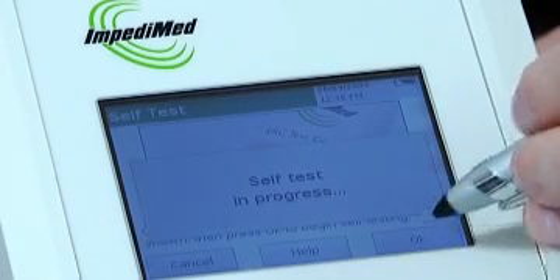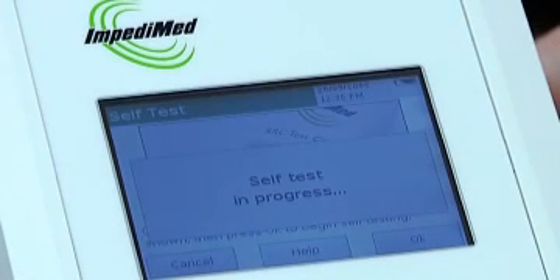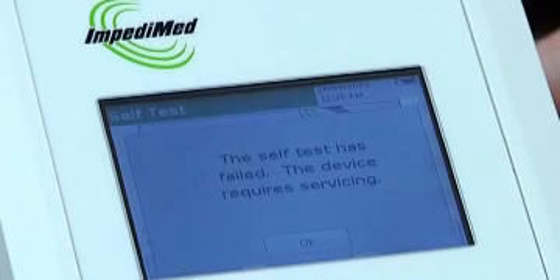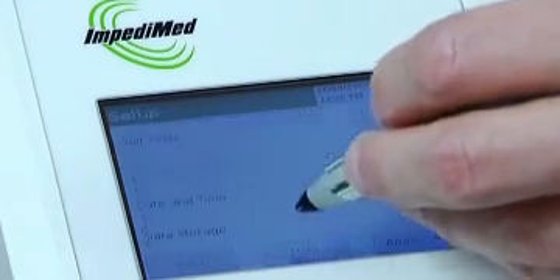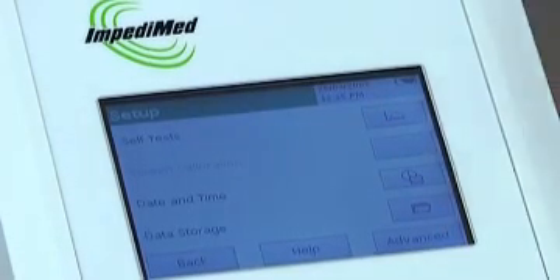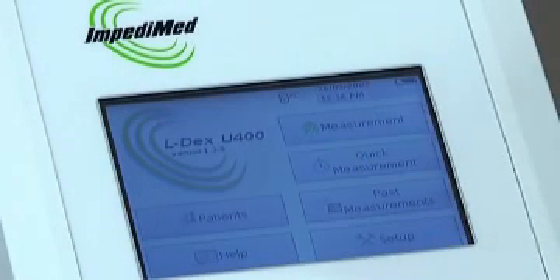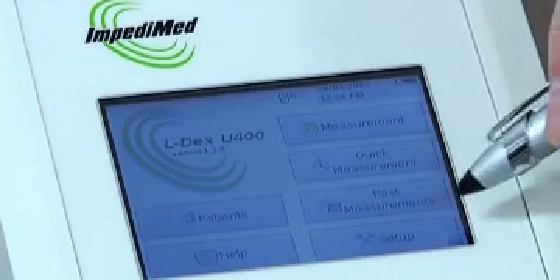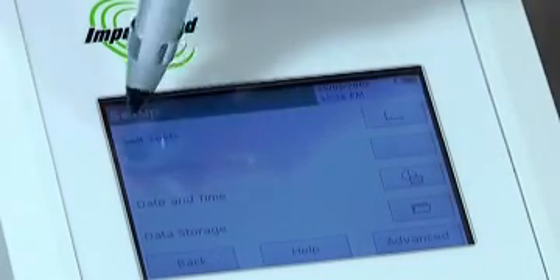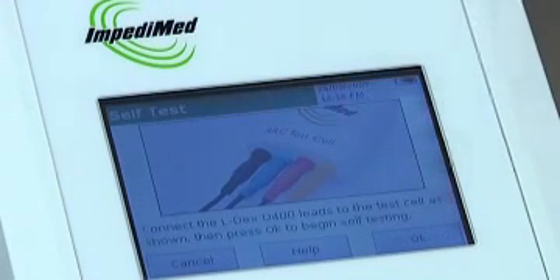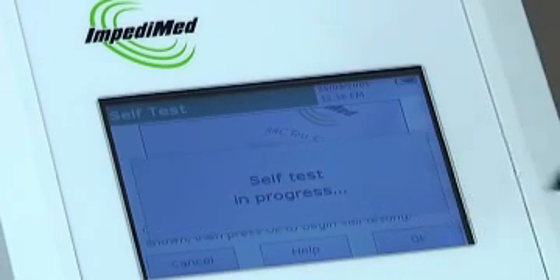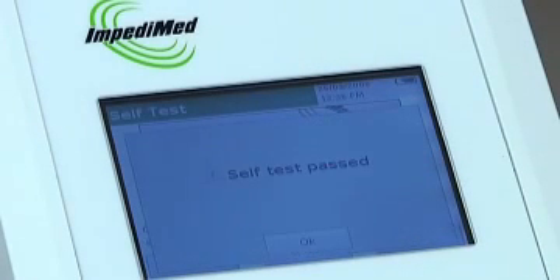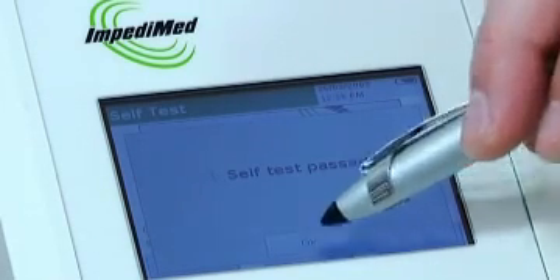The device will indicate that a self-test is in progress. If the device does not pass the self-test, a message will appear stating it has failed and the device requires servicing. You should not use the device if it does not pass the calibration check. Please call ImpediMed technical support for assistance. The device will display a self-test passed if the device passes the calibration check. The device is now ready for use. Press back to bring the device to the main screen.